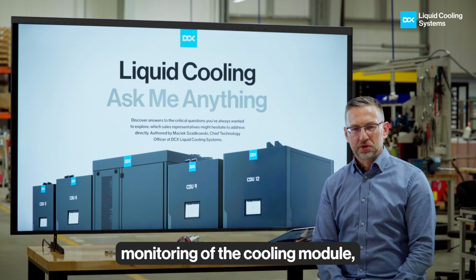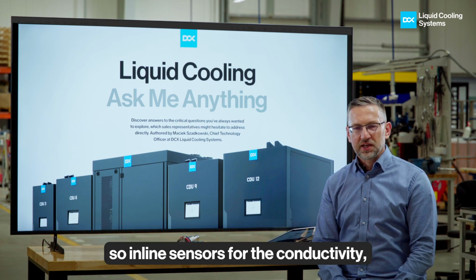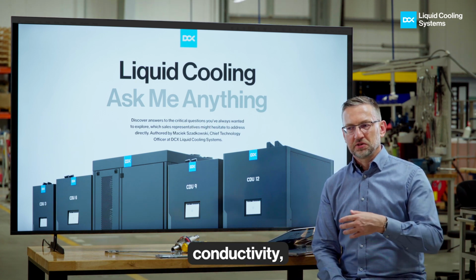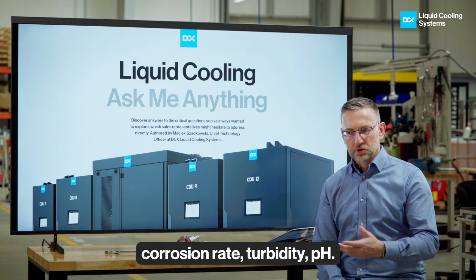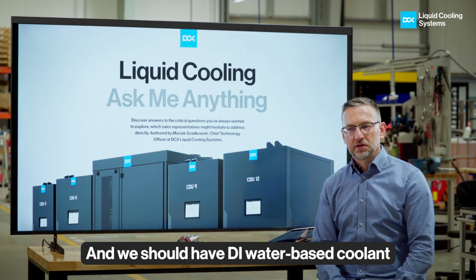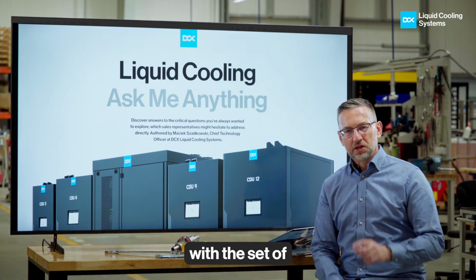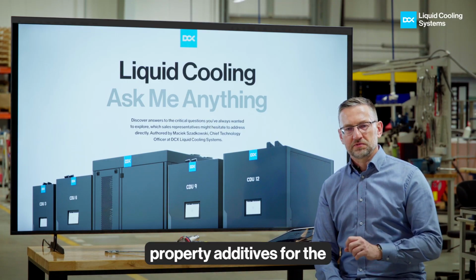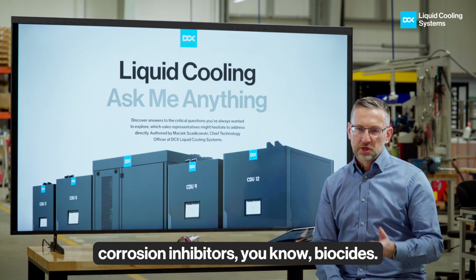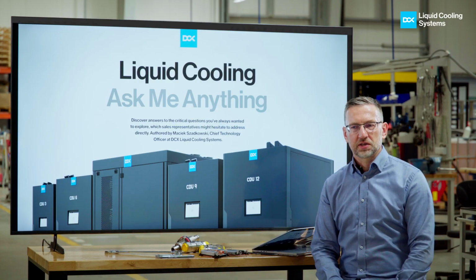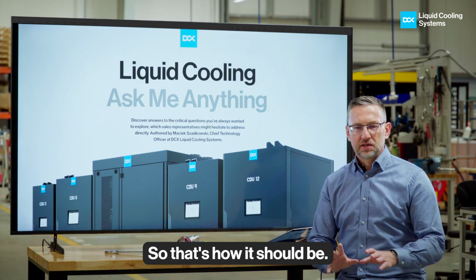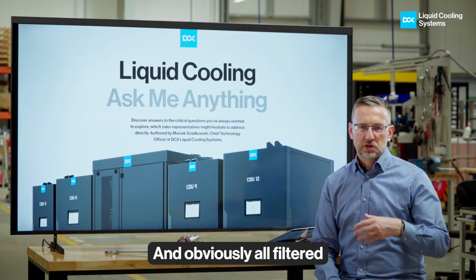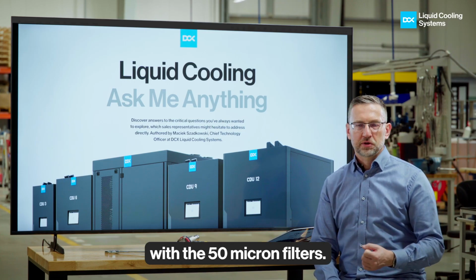So having continuous monitoring of the cooling medium, so inline sensors for conductivity, corrosion rate, turbidity, pH, and we should have DI water-based coolant with a set of proprietary additives for corrosion inhibitors, biocides. That's how it should be, and obviously all filtered with 50 micron filters.